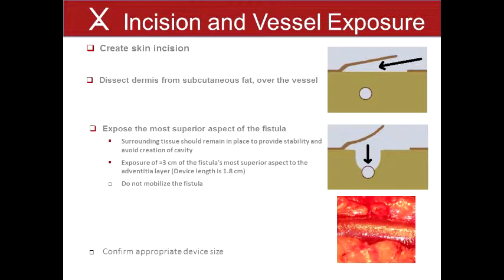To maintain fistula and VWING stability, do not mobilize the fistula. Fistula feeders may be tied off as needed. Although not common, the fistula may spasm due to the surgical exposure. When this occurs, the vessel diameter can be severely restricted and fall below the 5 millimeter requirement. It is critical that the vessel diameter be restored to 5 millimeters or greater prior to proceeding with the VWING implant procedure. Warm saline, proximal occlusion, or physical manipulation or flicking may help to bring the vessel back to an acceptable diameter. If the vessel remains below 5 millimeters in diameter, the VWING should not be placed.